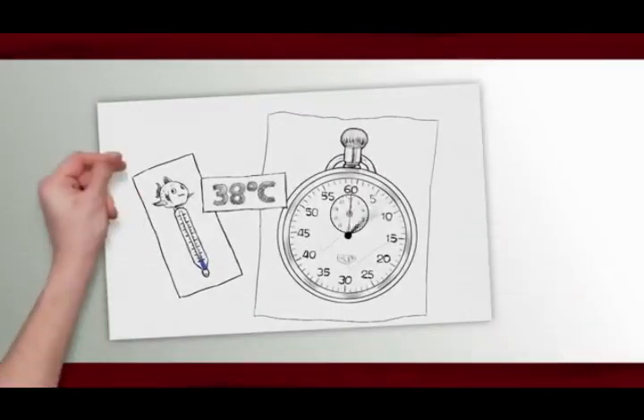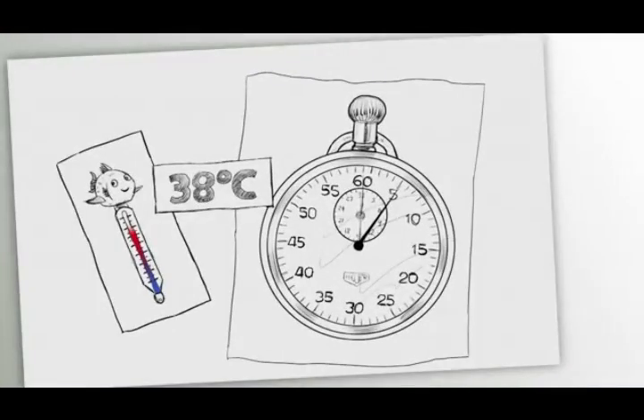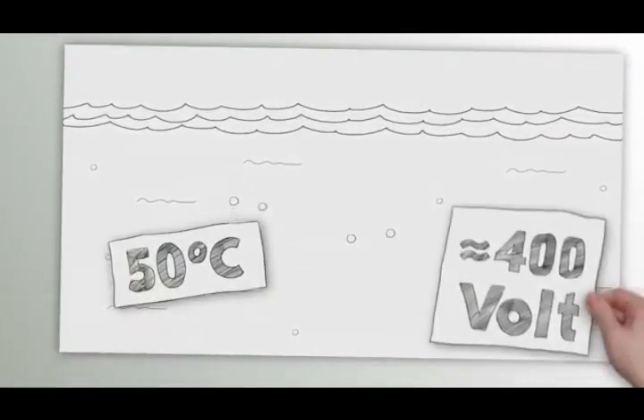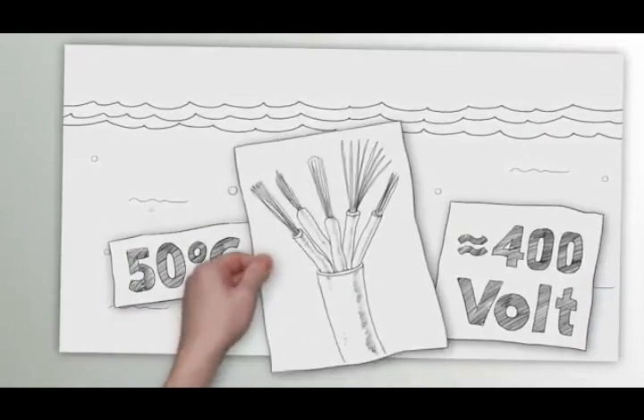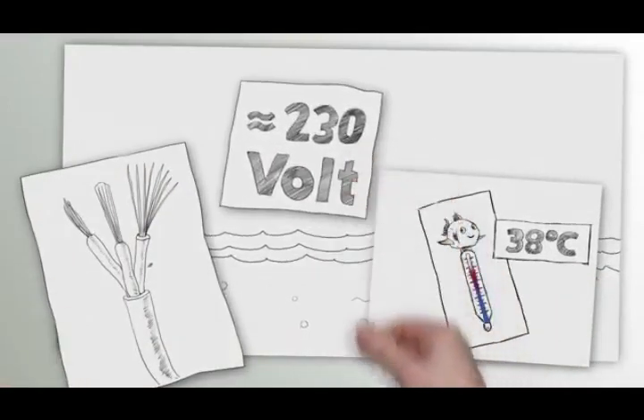Since instantaneous water heaters are based on the principle of heating water to the required temperature very quickly, these appliances need a lot of power for a short period of time. This is logical, and explains why, when they have to produce large amounts of water, supply several draw-off points, or reach very high water temperatures, they run on 400 volts. Here, three-phase power is absolutely necessary. For small amounts and lesser temperature increases, 230-volt appliances and a single-phase power connection are sufficient.